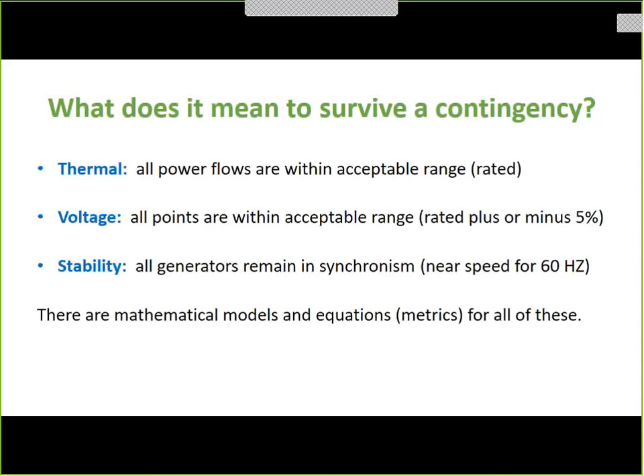You need good voltage. Actually, I've said this before. I get in trouble a little bit when I say it because it's not exactly the right thing we want you to think about. Really, what you pay for in your electric bill is voltage. That's what you want, right? If you've got a voltage, you're happy. So, megawatts and kilowatt hours, what is that? I mean, that's not even something you can touch. But a voltage you could touch. You wouldn't want to touch it if it's a big one. But a voltage you can measure and monitor very easily right there in your house. If you don't have a voltage, you've got a blackout. So voltage is an important quantity, and the criteria is rated voltage plus or minus 5%.